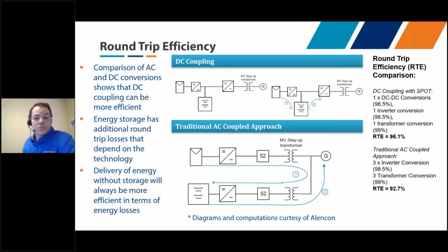We also wanted to talk about round trip efficiency, comparing a DC coupled system and an AC coupled system. In this top example, we've got a solar array and a DC-DC converter. That DC bus then flows over the top of the battery, and goes DC to AC out to the grid. In this application, if you want to charge the battery, it's only going through one DC-DC converter in order to match the stack voltage of the battery, so you get a round trip efficiency of about 96%.